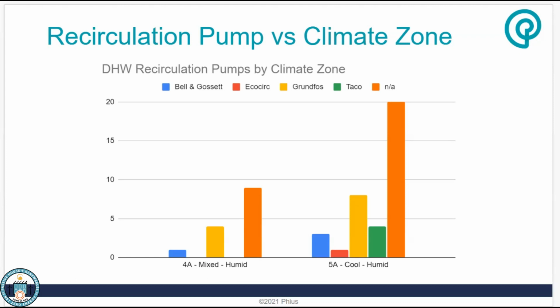continuous recirculation or time-based recirculation, which was much more popular maybe 15 or 20 years ago. That was basically the concept that, okay, people want hot water, we don't know when they're going to want it, so we're just going to run this pump 24/7 and run hot water throughout our buildings. It's kind of a big waste of energy. So these on-demand systems prevent that additional pump energy and also the hot water losses through these lines.